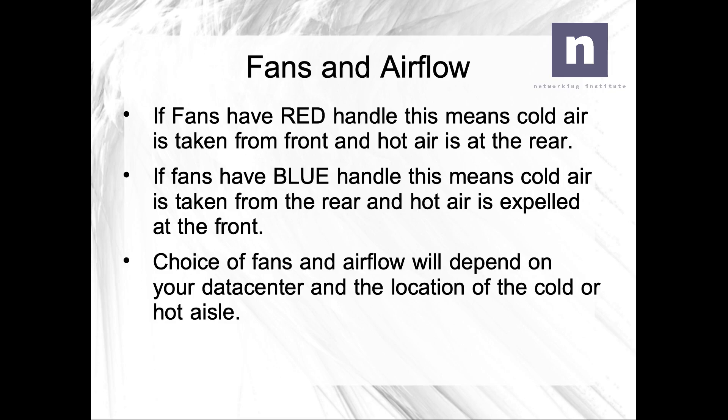Let's talk about fans and airflow. In the first video, one of the sample questions was: can you tell what the airflow of a switch is — front to rear or rear to front — based on the color of the fan handles? If fans have a red handle, cold air is taken from the front and hot air is expelled at the rear — that's why the fan has a red handle.